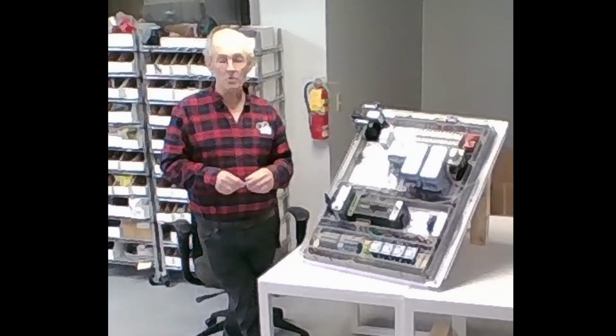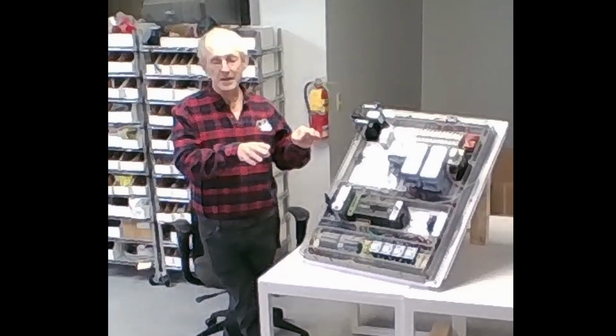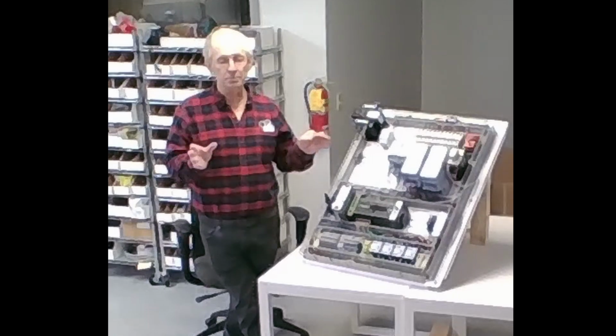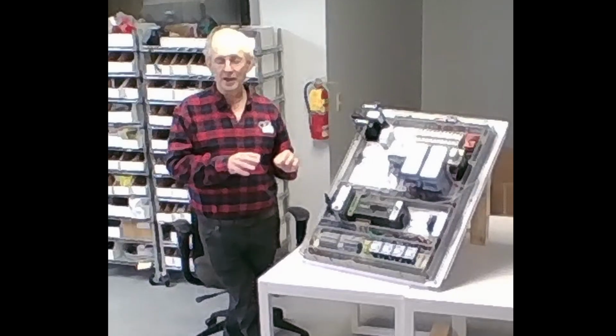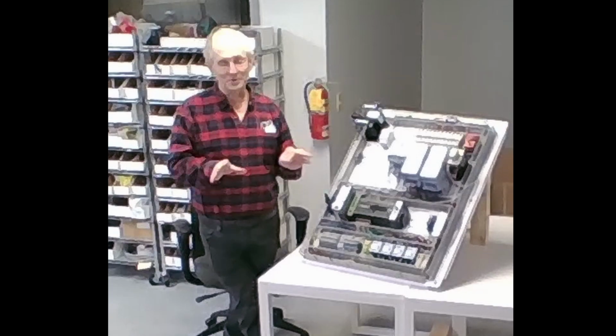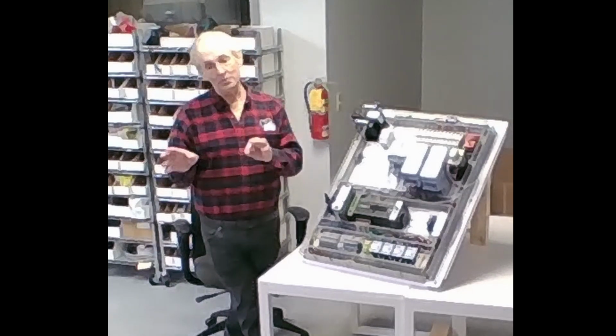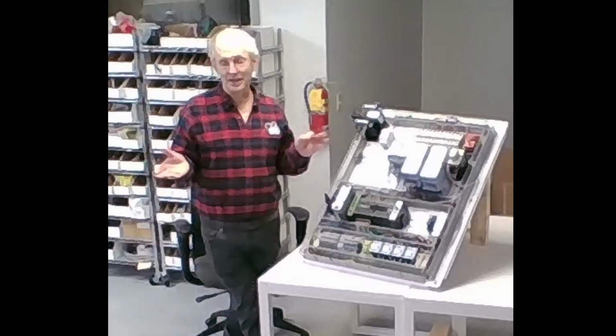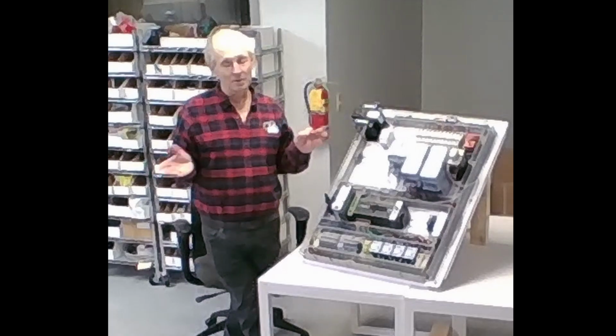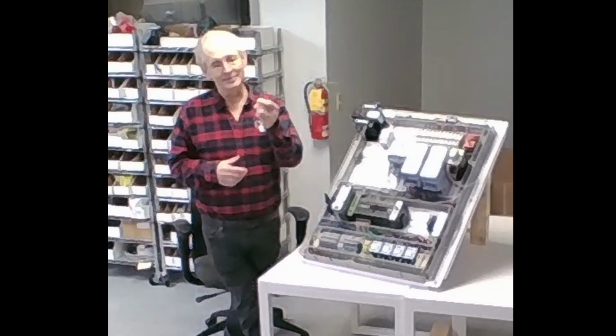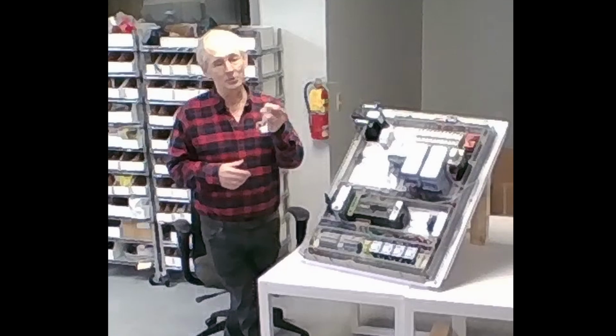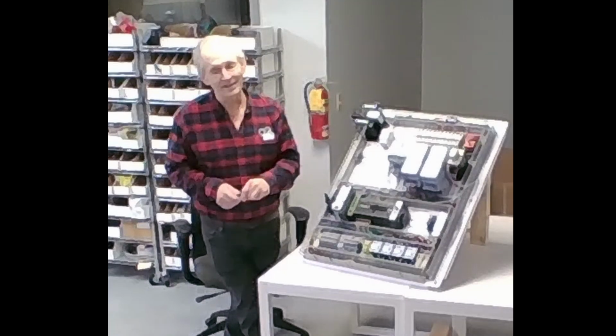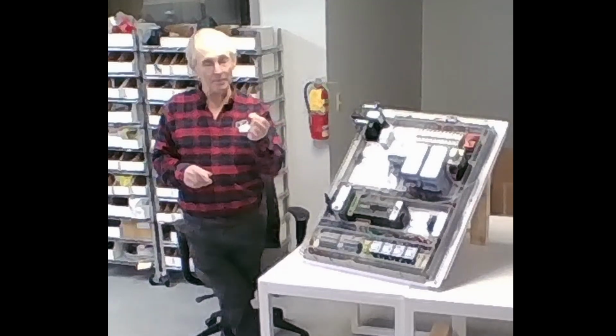In the case of the car washes, the blowers at the very end, they have really big blowers on undersized motors, and they use the service factor rating, and they actually overload the motor because it only runs for 30 seconds drying your car. But when you trip one fuse, the motor has no chance because it's overloaded already, and so it would burn the motor out. Right. So you can learn a lot by the fuses.